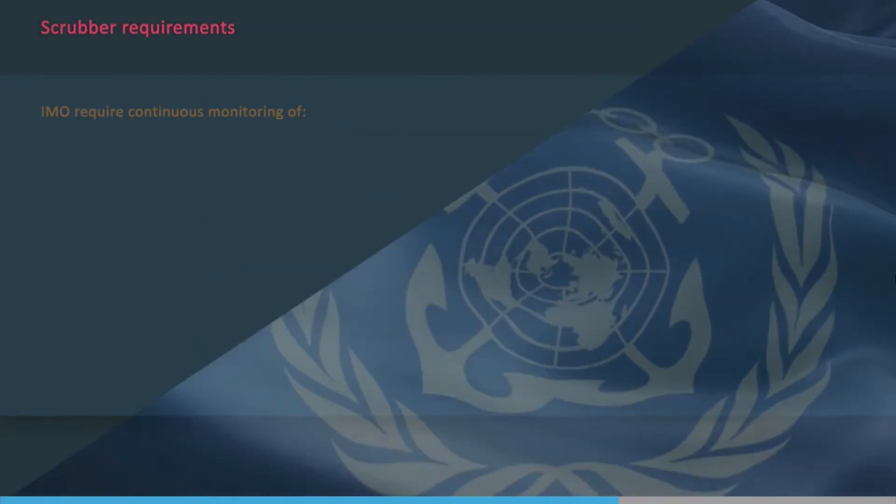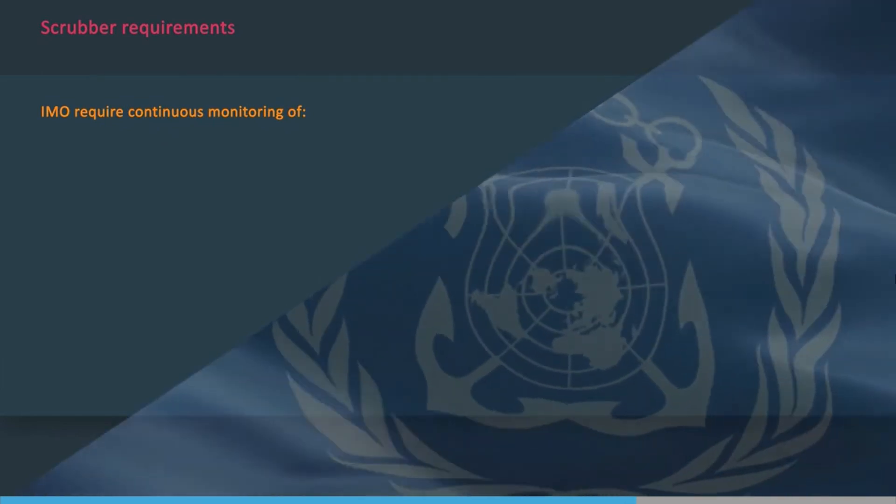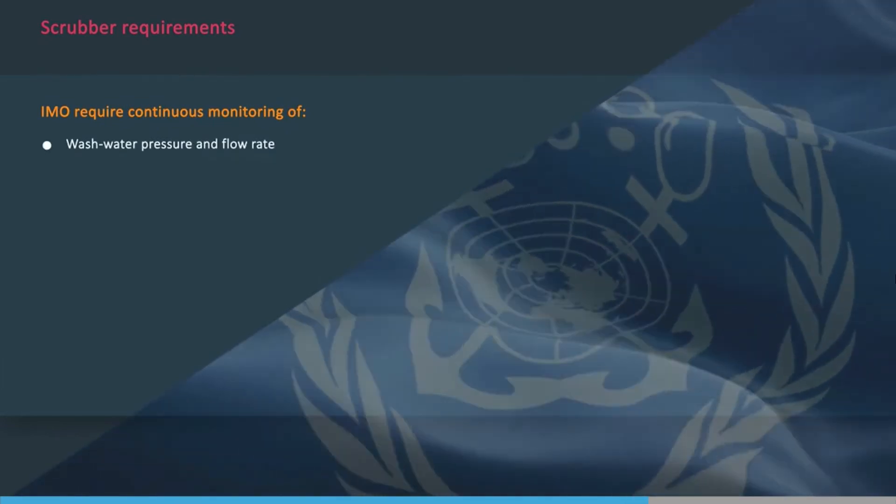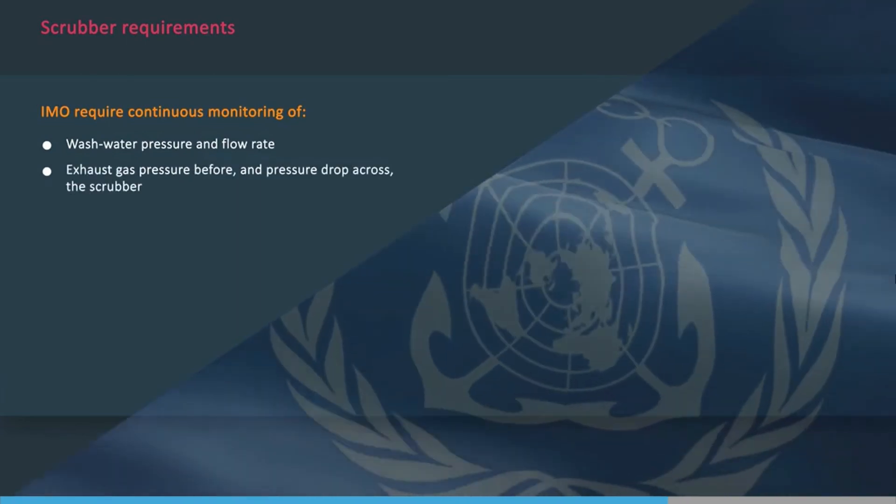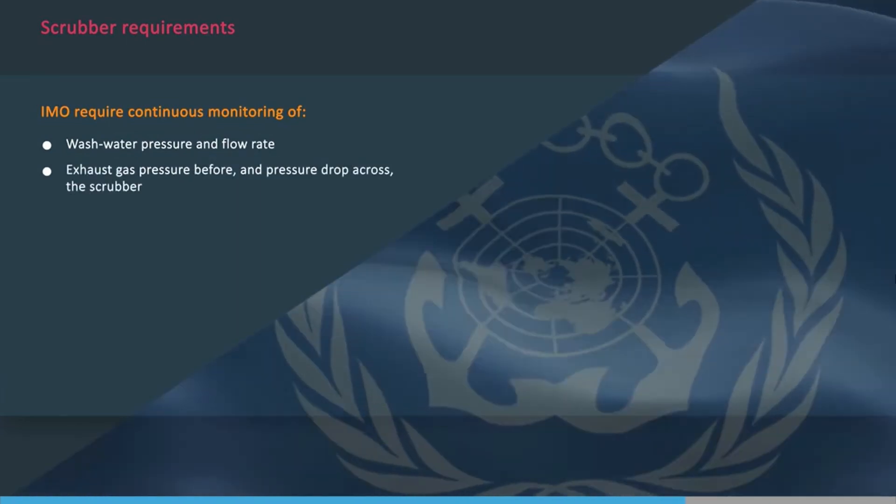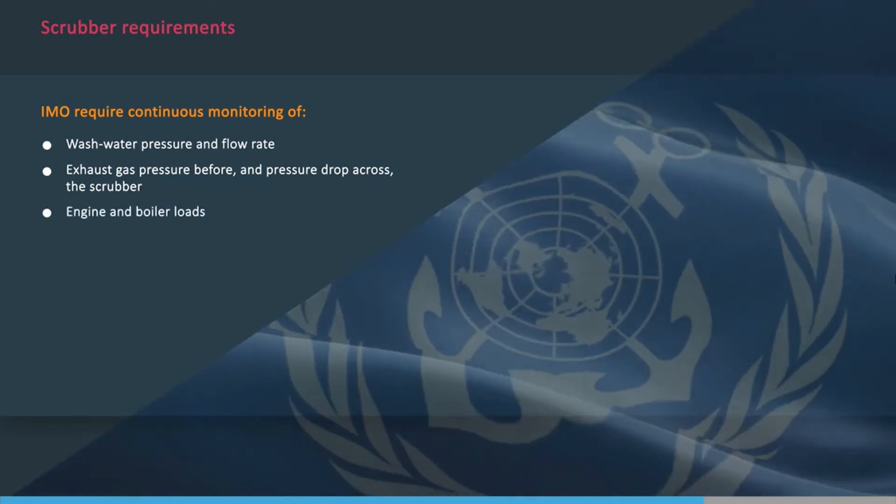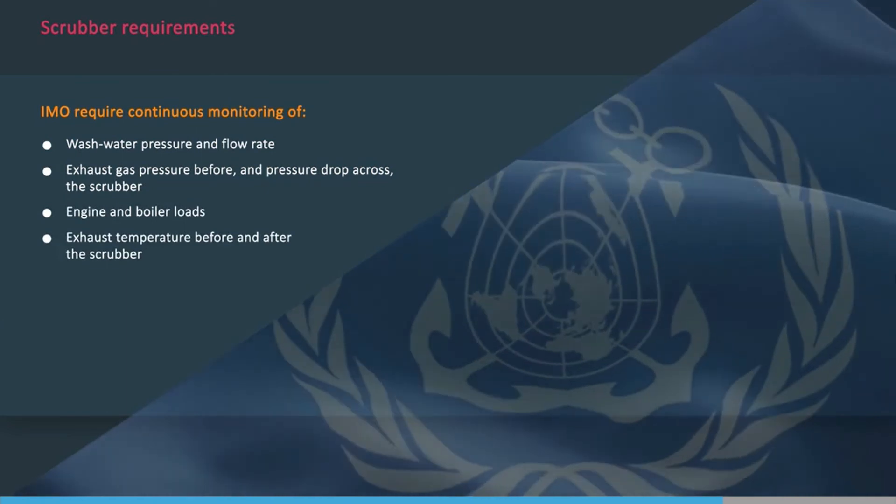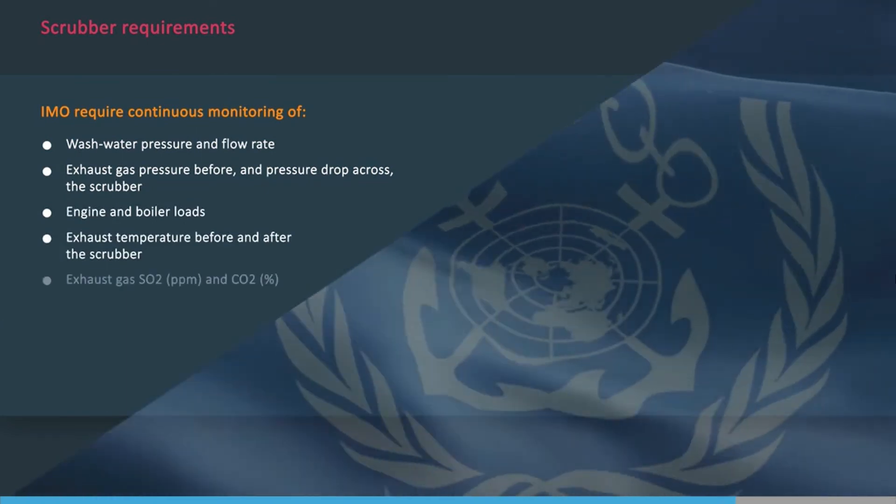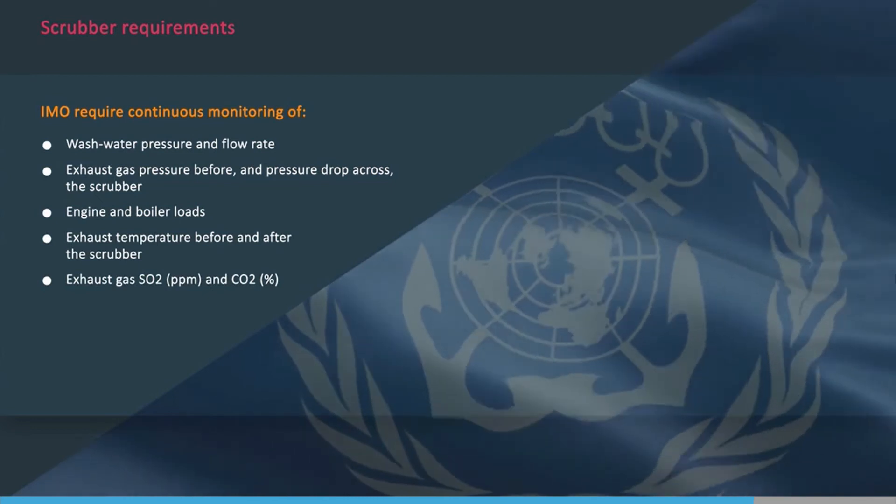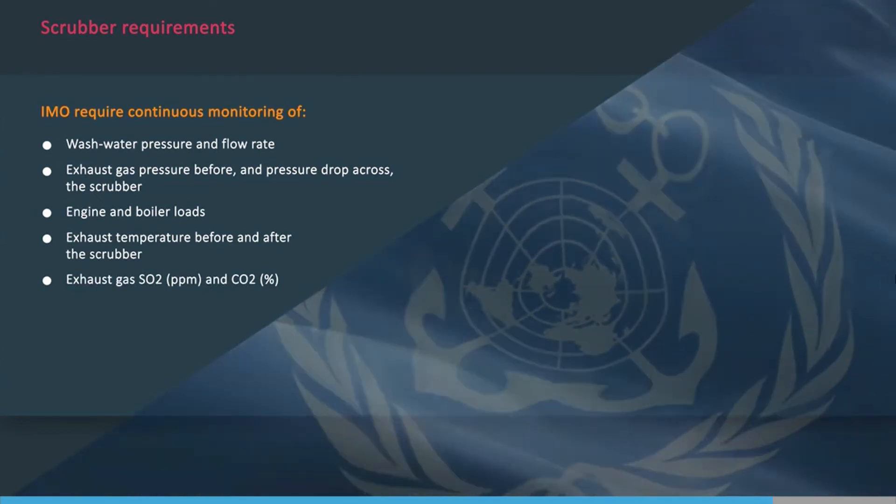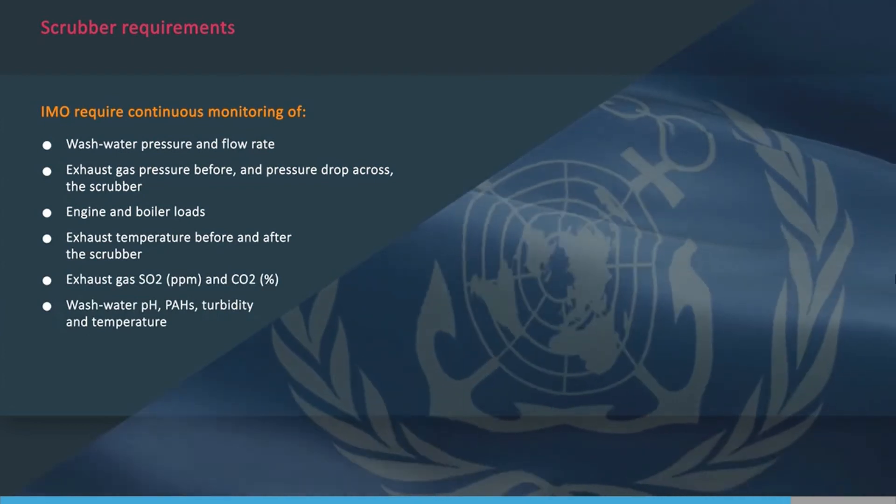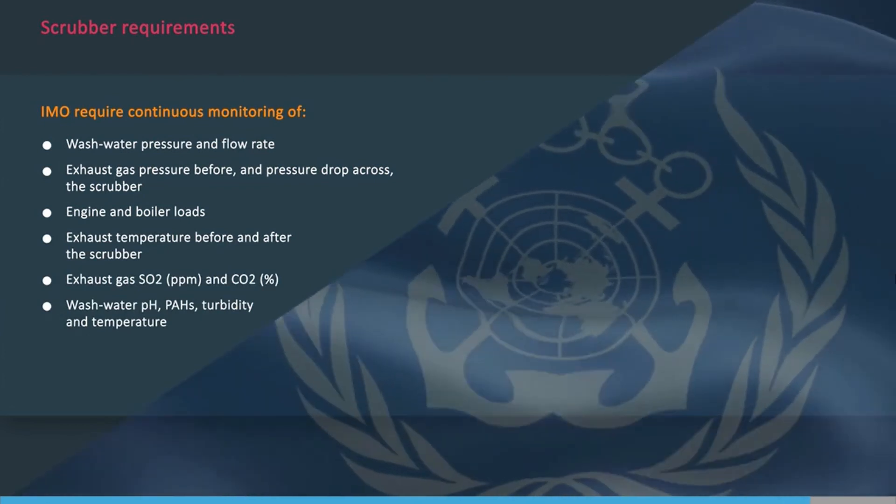The IMO require continuous monitoring of wash water pressure and flow rate, exhaust gas pressure before and pressure drop across the scrubber, engine and boiler loads, exhaust temperature before and after the scrubber, exhaust gas sulphur dioxide parts per million and carbon dioxide by percentage, wash water pH, PAHs, turbidity and temperature.